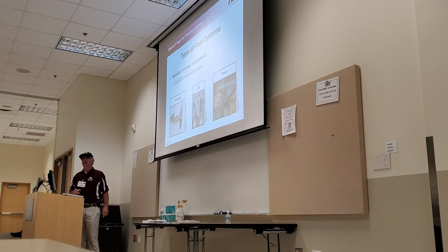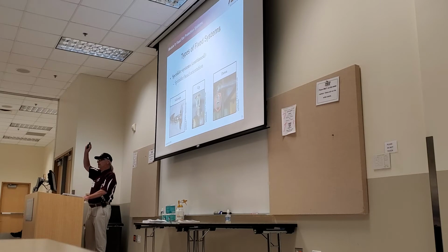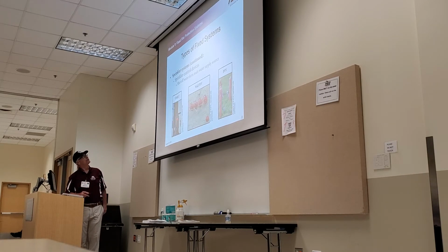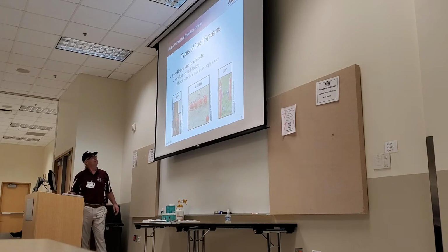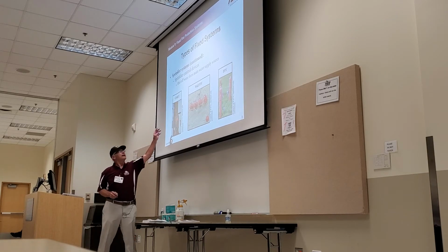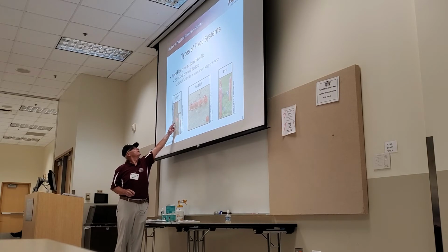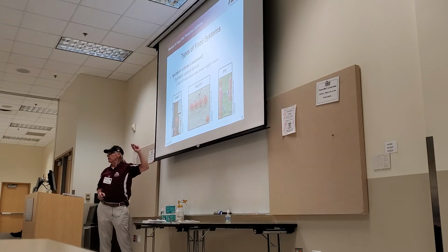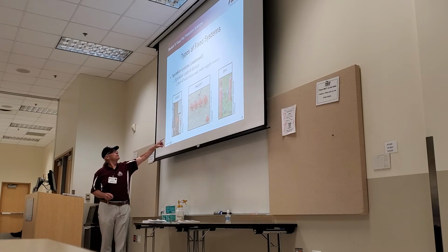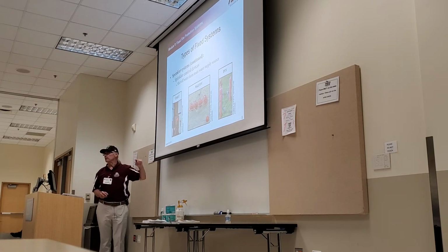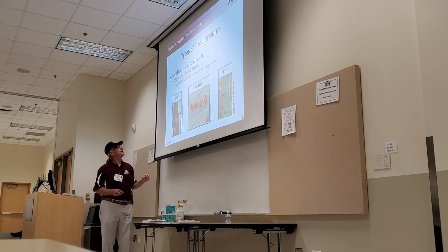This is a wet system. This is charged all the way to the heads, and it's waiting for that. And then the next one of those, well, let's go over the OS&Y valves. Here's an OS&Y. If they're in a system where you have a fire alarm panel monitoring, these are tamper switches where you can tell if they're open or closed. And if they're in the wrong position, they'll send a trouble signal to your fire alarm panel. And that'll be a yellow light on that.